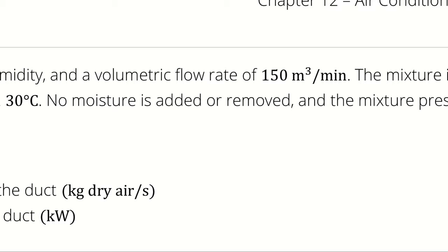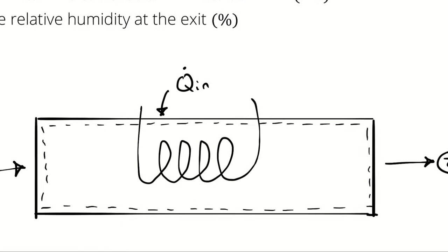The answer is yes — it is all of them. Because when we're modeling psychrometric behavior, we are using Dalton's law to approximate the behavior of air and water vapor mixed together. Dalton's law assumes that all of the species in the mixture occupy the same volume. Therefore, the volumetric flow rate of the atmospheric air, the dry air, and the water vapor are all 150 cubic meters per minute.